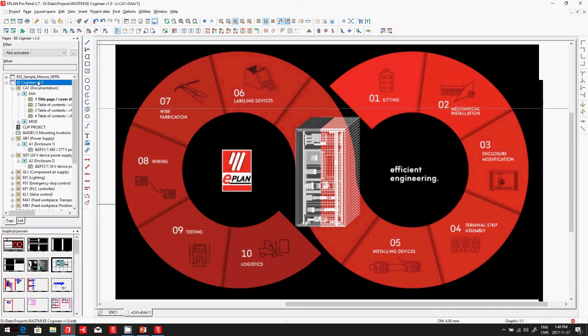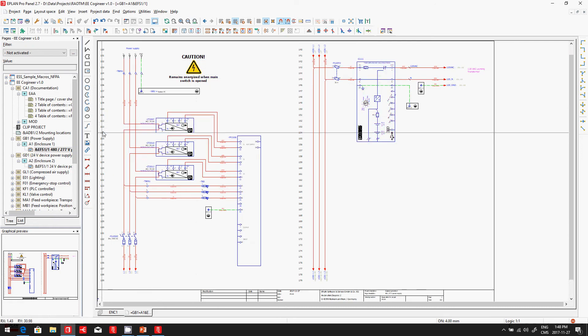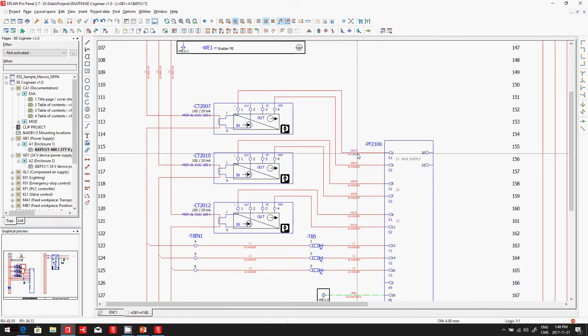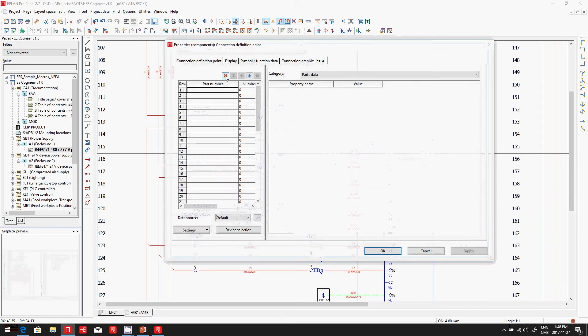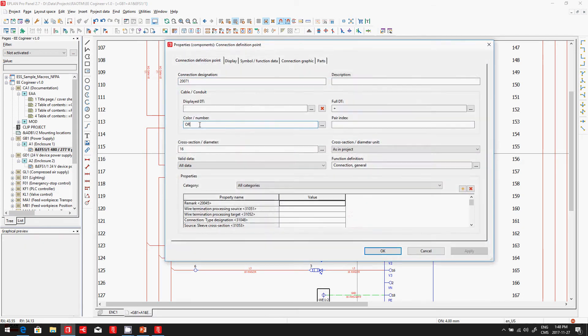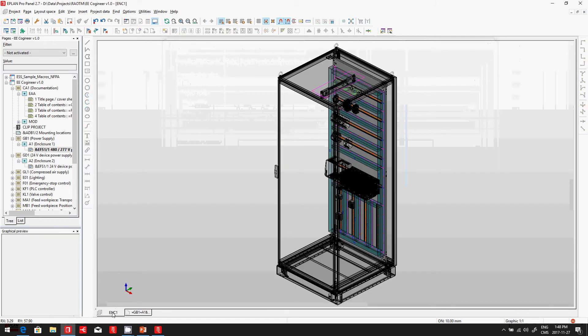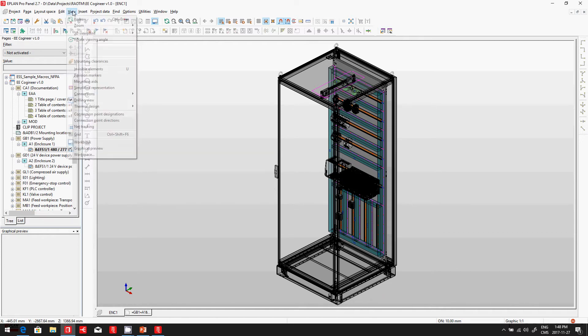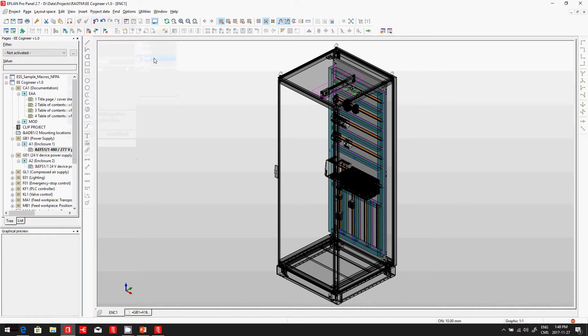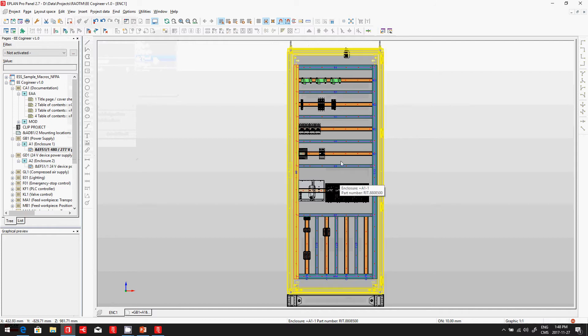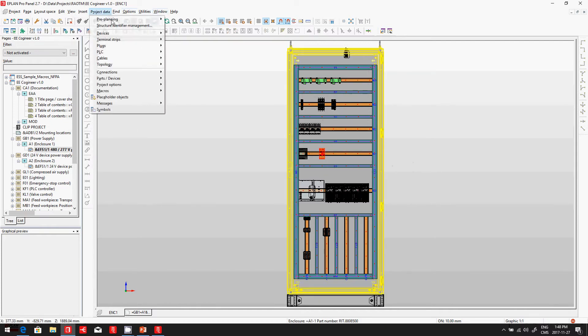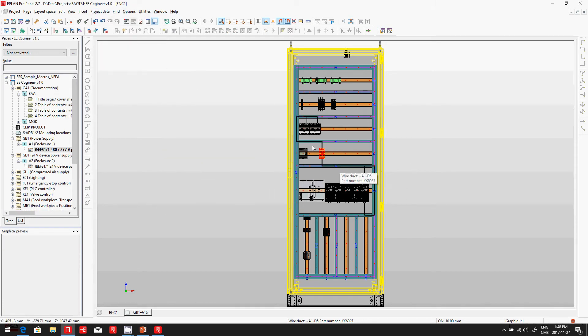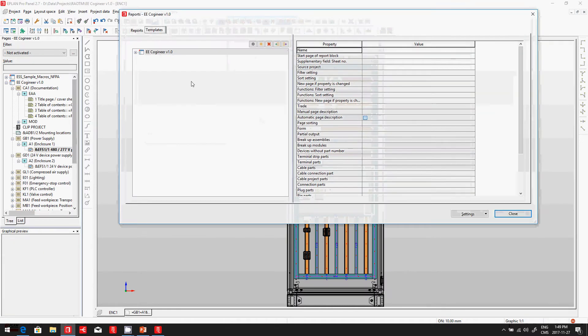First of all, you know that the schematics were created here from scratch with ePlan. Within ePlan schematics, we have devices that are connected through wires to another device connection point. So every wire has a certain color, a certain gauge, and the length is calculated based on what we've done here on the ePlan side. If we actually select one of these components, let me just look at the front view here, and let's say we pick one of the devices, we can actually show the different wires.